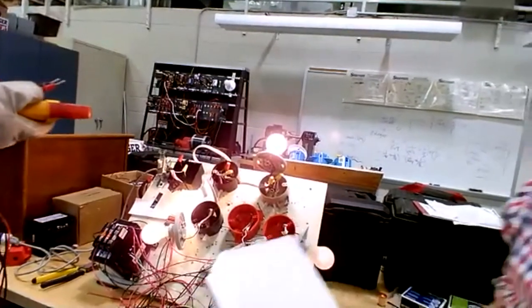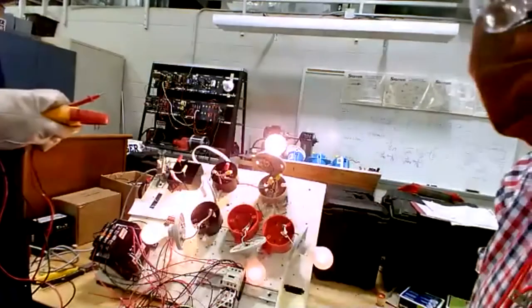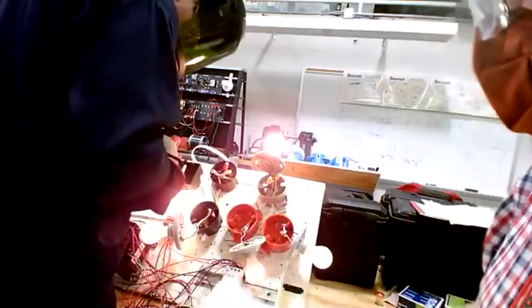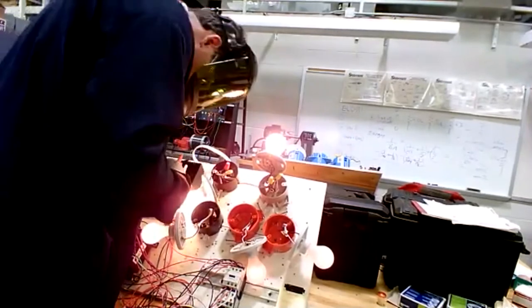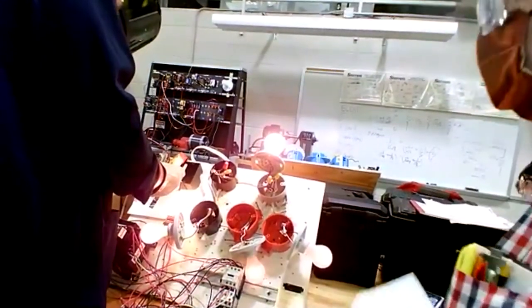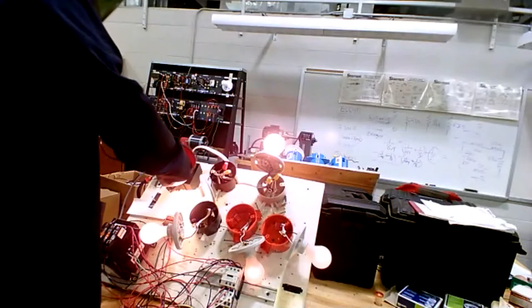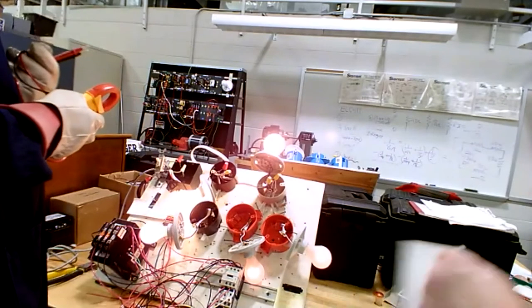So the lab starts out and they ask you to measure the total circuit current on number 19. So go to amps and use that clamp there and go up where you leave the switch, before it goes to any distributor in there, and get the amp reading. Right. That's what you get. 0.92 amps, and you see on mine, when I did mine back a few years ago, it was like 0.83. That's close enough. That's fine. 0.92. That's for number 19.